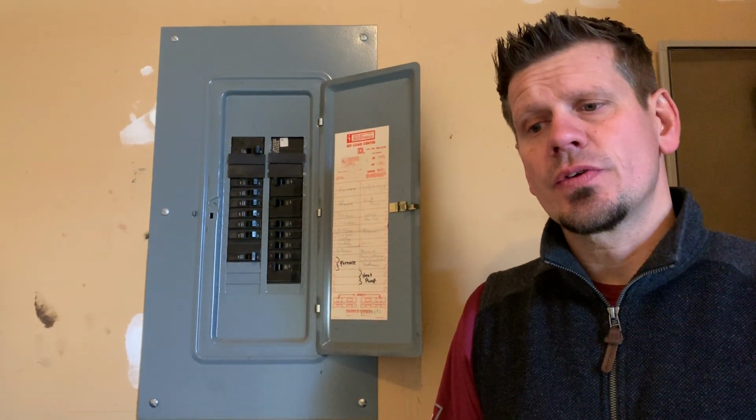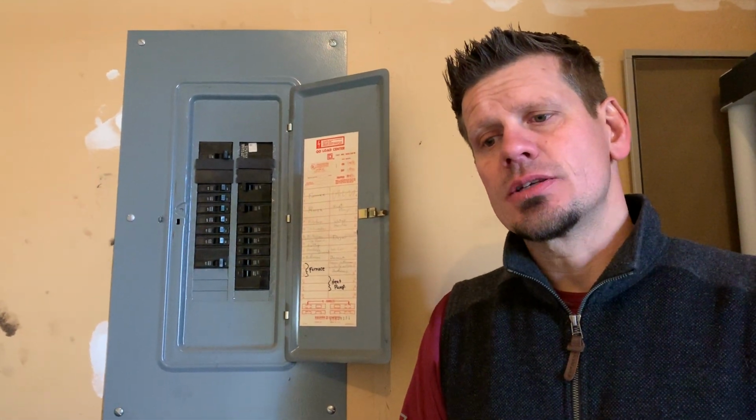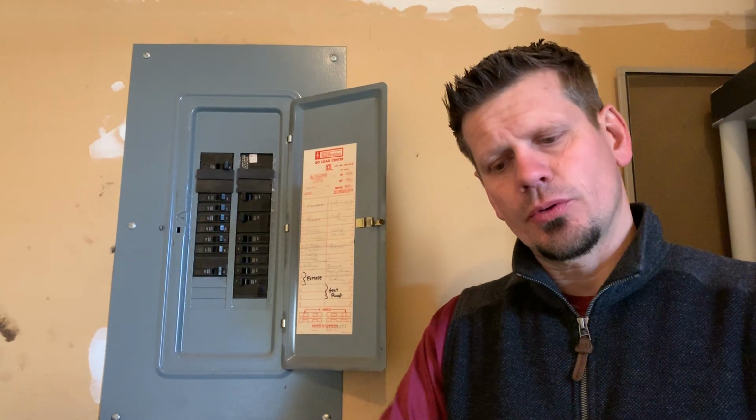The other thing you can look for is very odd things, but I've had it where one time a lag for a pergola was put in and it nicked the hot side, the ungrounded conductor on a branch circuit inside a guy's bedroom. I have a YouTube video on it from 9 years ago, and I consistently watched that disc meter slow down and speed up, slow down and speed up as I pulled the neutral on and off. That's a very rare occasion. The complaint was the guy was putting up Christmas lights and got blown off his ladder, getting shocked, and also that the gutter was energized. It was energized through the flashing to the gutter to the ground. I have a light bulb I put on the grass and put in a little ground rod.